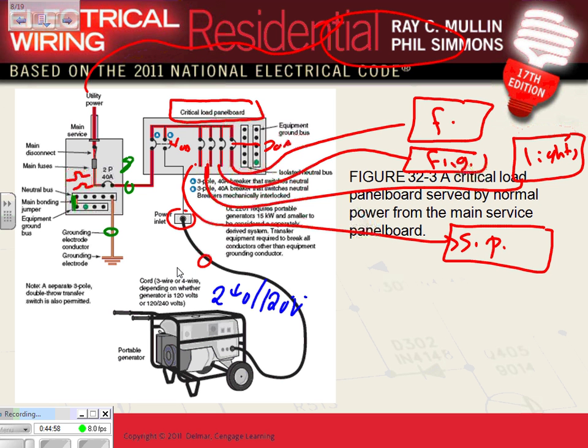Chris, one thing you don't do here is you don't bond the neutral and the ground at the second panel. This is called separately derived system. Where do we have that one? It's called separately derived system, right in here. Does that mechanism isolate the neutral as well as the hot conductors up on the lower left? This is a separately derived system. Does this mechanism isolate the neutral as well? If it's a separately derived system, it should be.